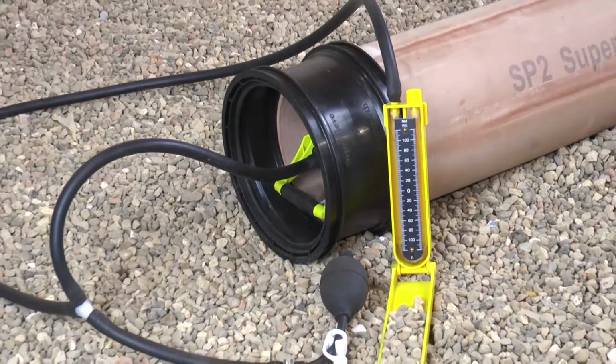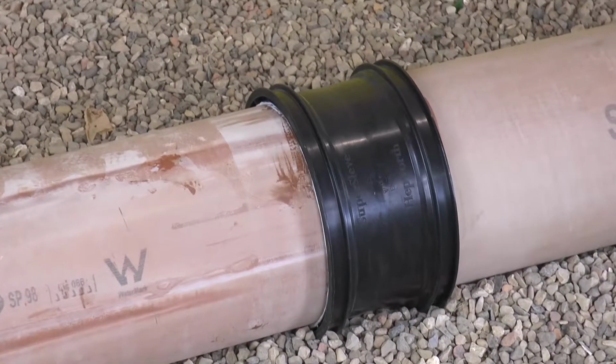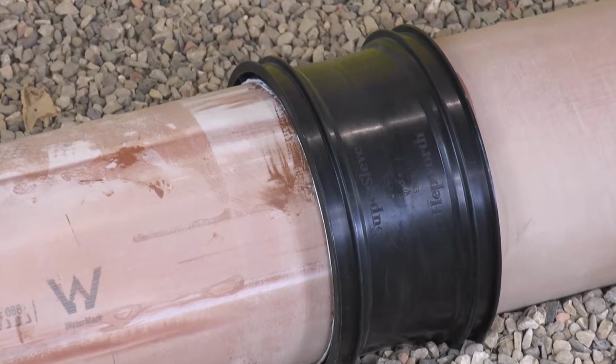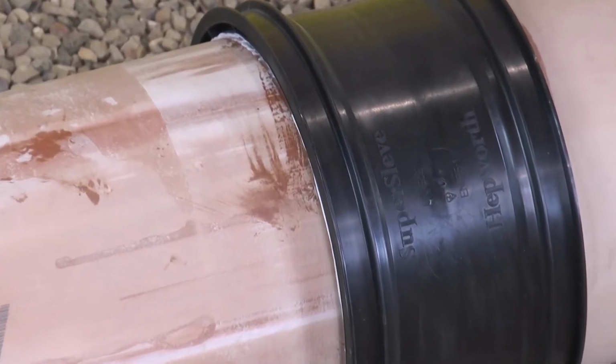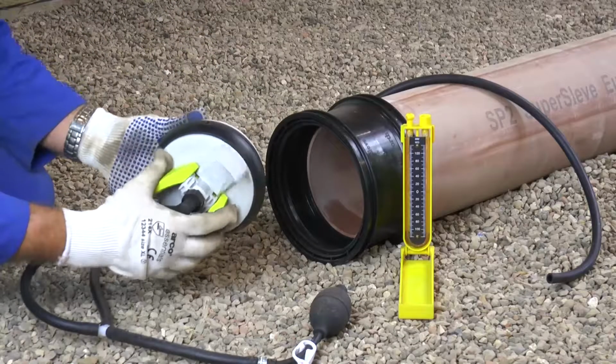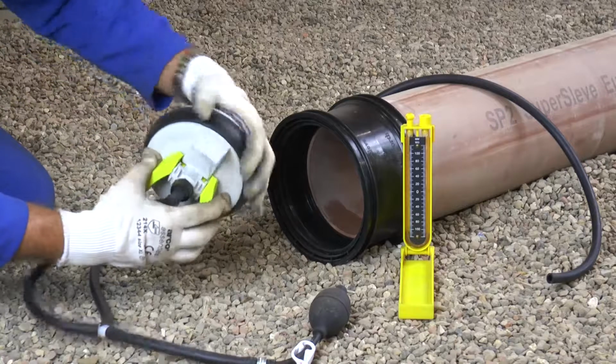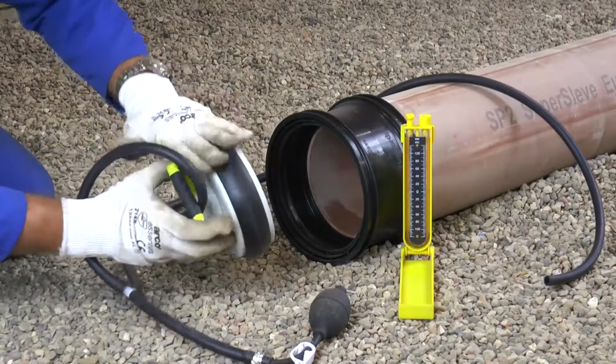Now we are looking for less obvious faults. The equipment may be in place, but could be a very poor fit. This is the most difficult type of fault to determine, and often the pipeline is blamed for the fault at this point. It is much simpler and easier to check the testing equipment first. Check each testing component sequentially.